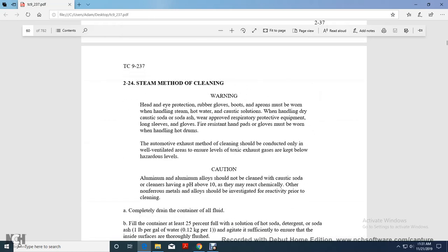Alright, 224, steam method of cleaning. Warning: head, eye, and face protection, rubber gloves, boots, and aprons must be worn. When handling steam, hot water, caustic solutions, dry caustic soda or soda ash, wear approved respiratory protective equipment, long sleeves and gloves. Fire-resistant hand pads and gloves must be worn when handling hot drums. Automotive exhaust method of cleaning should be conducted only in well-ventilated areas. Ensure levels of toxic exhaust gas are kept below hazard level.